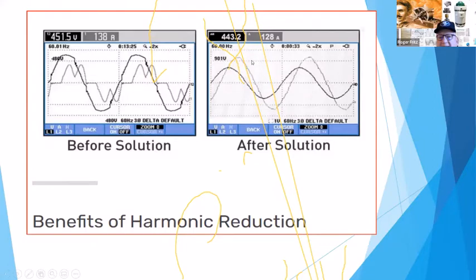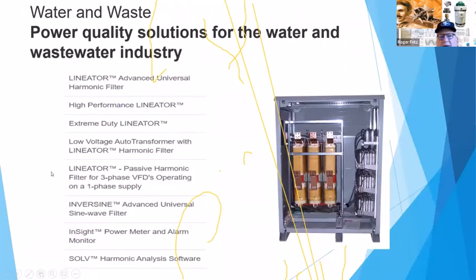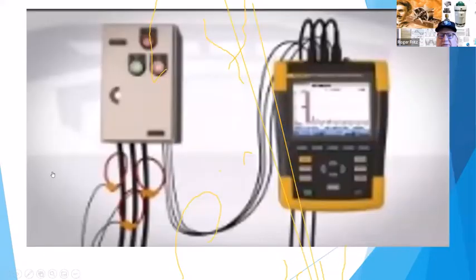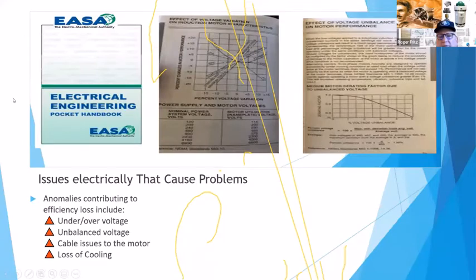So it is an important factor, and if you take 10 kilowatts and you do the math on that, 10 is roughly 80,000 kilowatt hours. At 10 cents a kilowatt hour, that's $8,000 a year different in operating cost, depending on where the harmonic capability is proper in an application. So it is important to look at these factors as you're going forward, to maintain that cause and effect issue that happens inside the motor.